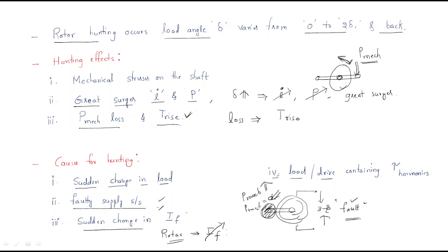Fourth cause: load or drive containing torque harmonics. Torque is the main reason for synchronous motor rotation, so if the load torque or drive torque contains harmonics, hunting will develop. In summary, the causes are: sudden change in load, faulty supply voltage, sudden change in field current, and load/drive containing harmonic torque.